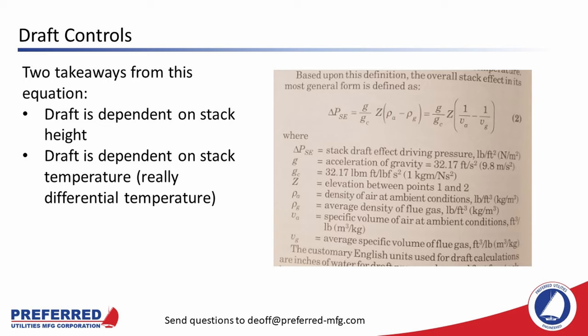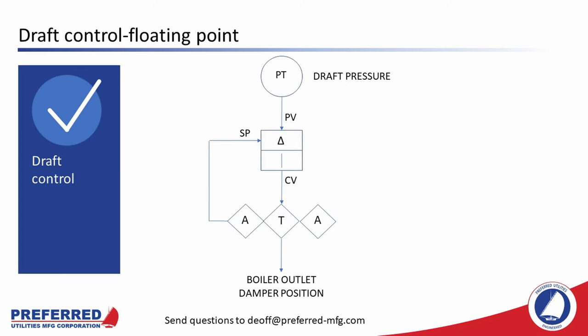The simplest type of draft control is known as floating point control. It utilizes a draft transmitter at the boiler outlet — at the bottom of the stack but above the stack outlet damper. There is one set point for all firing rates, usually just slightly negative, and the outlet damper is positioned to maintain the draft set point. Control is proportional only, with a dead band where no corrective action is taken if the draft is close to set point — this reduces boiler outlet damper hunting. Essentially, with floating point draft control, close is good enough.